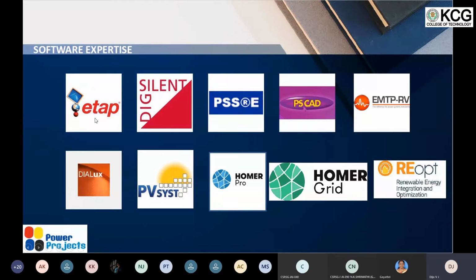One is ETAP software, which is used for power system studies, for load flow, short circuit, transient stability, motor starting, all power system studies. DIGSILENT is also similar, but the power protection coordination part is a little more detailed in DIGSILENT. So we generally use DIGSILENT for some of the protection coordination studies, but ETAP also has similar, but for some specific protection coordination studies we might need to use DIGSILENT. Then PSSE is also similar software. ETAP, DIGSILENT, and PSSE are almost similar software for the power system studies.